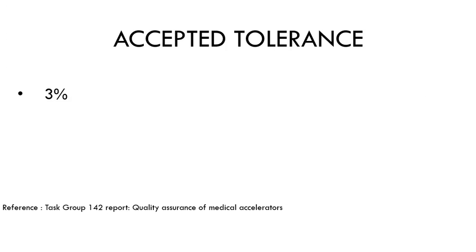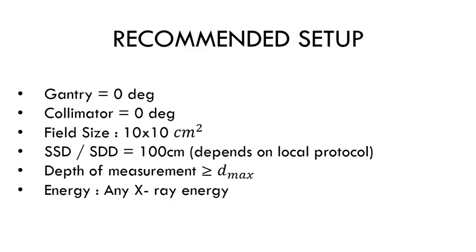Accepted tolerance is 3%. Recommended setup: gantry zero degrees, collimator zero degrees, field size should be 10 by 10. SSD or SDD equal to 100 centimeters. This value may also depend on the local protocols.